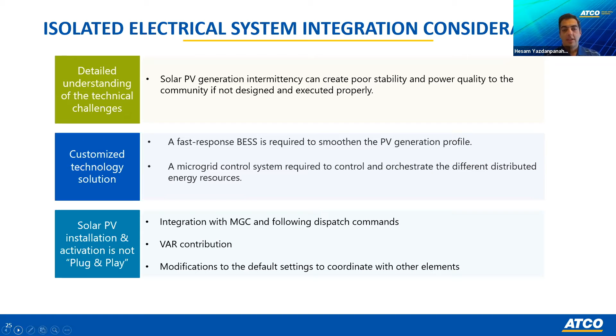The other challenge is you cannot rely on the factory default settings for over voltage, under voltage, or frequency or under frequency settings. You need to coordinate and change these settings in your inverters so that they match whatever you have in the microgrid. You cannot afford tripping them too soon or too late. Next slide, please.